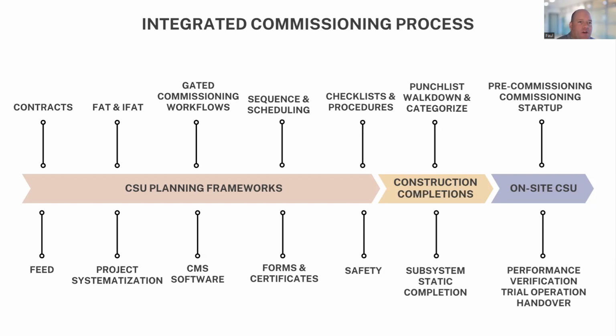The last portion is our on-site commissioning and startup, and there are six project management frameworks required there. These are some of the stages of commissioning you'd be somewhat familiar with: pre-commissioning, commissioning, and startup. Pre-commissioning is our equipment level tests, just testing the pump on its own. Commissioning is testing things as a group of equipment where we expect that group to function as a subsystem or system. As we go through those individual equipment tests and system tests, moving toward startup, we introduce process fluids or do first energizations for the first time, then move through performance verification to fine-tune the systems, trial operation to make sure everything's correct one final time before we move to handover of the systems. All of these frameworks for on-site commissioning and startup are managed and tracked within our commissioning software to manage our commissioning workflow.